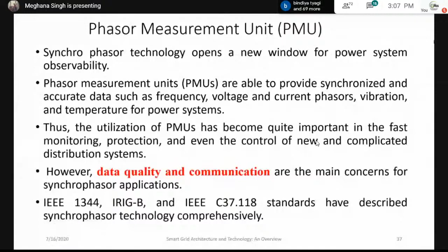Getting synchronized, accurate data is why I'd prefer PMUs over SCADA. Utilization of PMUs has become important for fast monitoring, protection, and control of complicated systems. However, data quality and communication are the main concerns for synchrophasor applications. The communication technology used should be very high-end, not less than 4G, preferably 5G, since everything is time stamped and accurate data is essential. Standards like IEEE 1344, IRIG-B, and IEEE C37.118 deal with synchrophasor technology comprehensively.